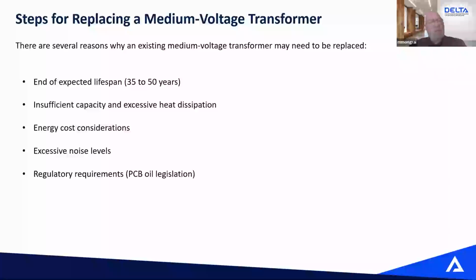A transformer's life expectancy can be somewhere from 35 to 50 years. We've seen some with longer life, but still, at some point they're going to need to be replaced. There are many reasons why we need to replace a transformer, whether it's a power transformer or a low voltage unit. The transformer can be at the end of its life. We may have more load demand than the capacity of the transformer. The transformer may be old with no efficiency, so lots of heat rejection in the room and energy cost considerations. Some older units can be quite loud in regards to the noise they emit. At some point, we did a lot of liquid fill, PCB oil liquid fill transformer replacement to be compliant with government regulations. So there are many reasons to replace a transformer.